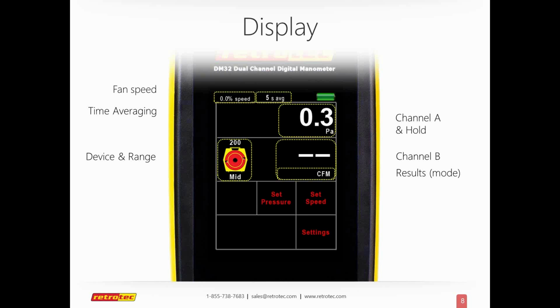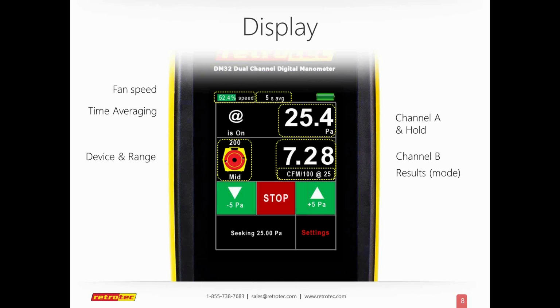So here's what the screen looks like when it's running as an active test. You can still see that the range and the device are all still there. Now you see a green line at the top where my fan speed is. And now I have the pressure that I'm running. And now my results are not just CFM, but I can actually have the gauge give me the results live. So here I actually have it set up for a duct test, and I'm reading CFM per 100 square feet at 25 pascals.